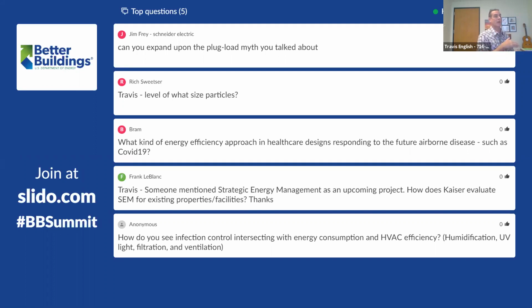But to get straight to the bottom line, in medical office buildings we don't see high plug loads—the average winds up at about 0.5 watt per square foot. In surgery centers you'll get up to 1 watt per square foot, but over the course of the day it goes below that. Plug loads in patient rooms are ridiculously low—it's basically a TV in the room, and maybe some equipment running at the headboard. The plug load in the patient room is less than the plug load in my living room on a square foot basis.